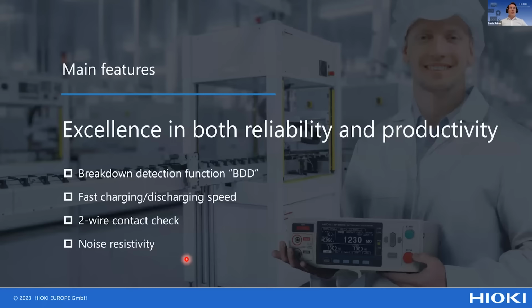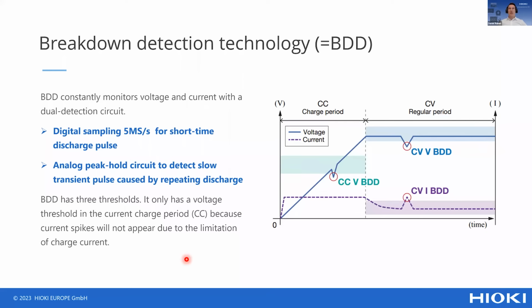So what Hioki came up with is a device specifically tailored for the battery industry. We have four main features, which were shown at the beginning, and we want to tell you about them in more detail now. They are the breakdown detection function, increased charging and discharging capability, a two-wire contact check function, and noise resistivity. And in this chapter, we want to show you why it is especially interesting also for the production side. The first part is the breakdown detection technology. We call it breakdown detection technology because what we currently see in the market is a partial discharge detection technology, but only looking at the voltage side.